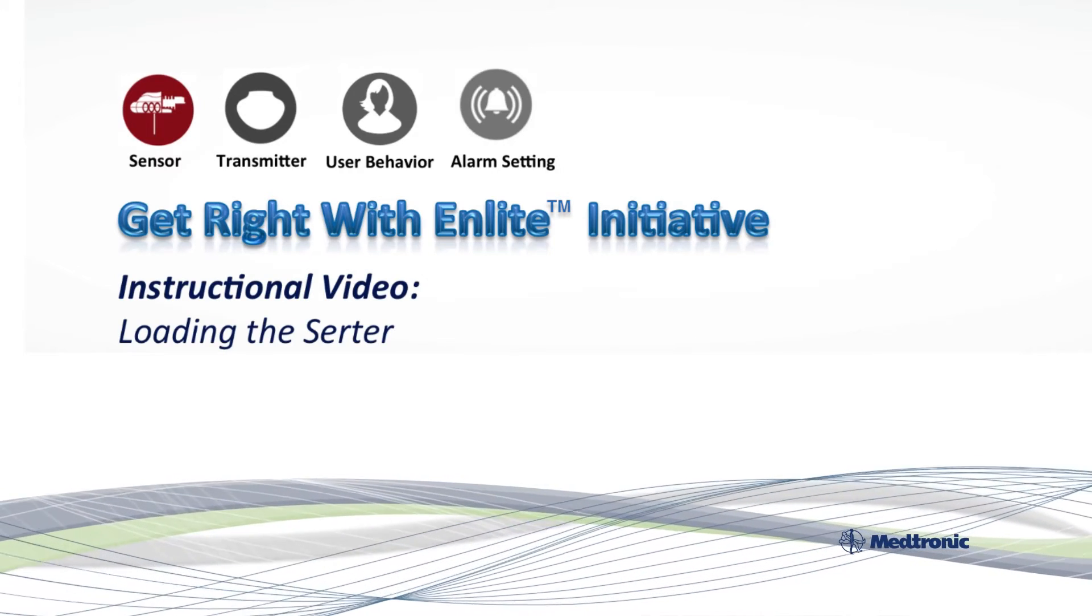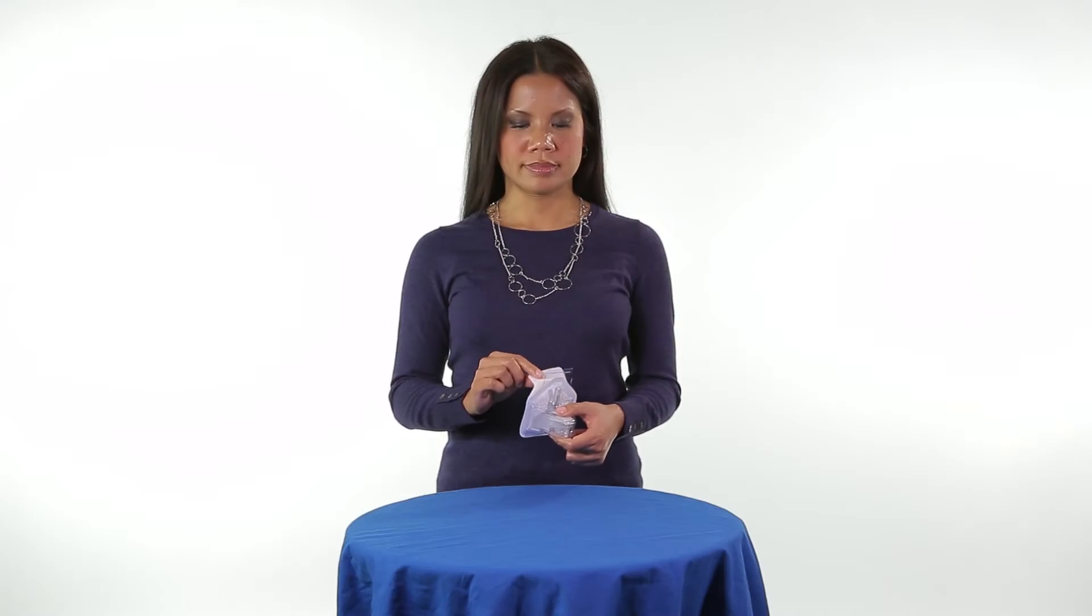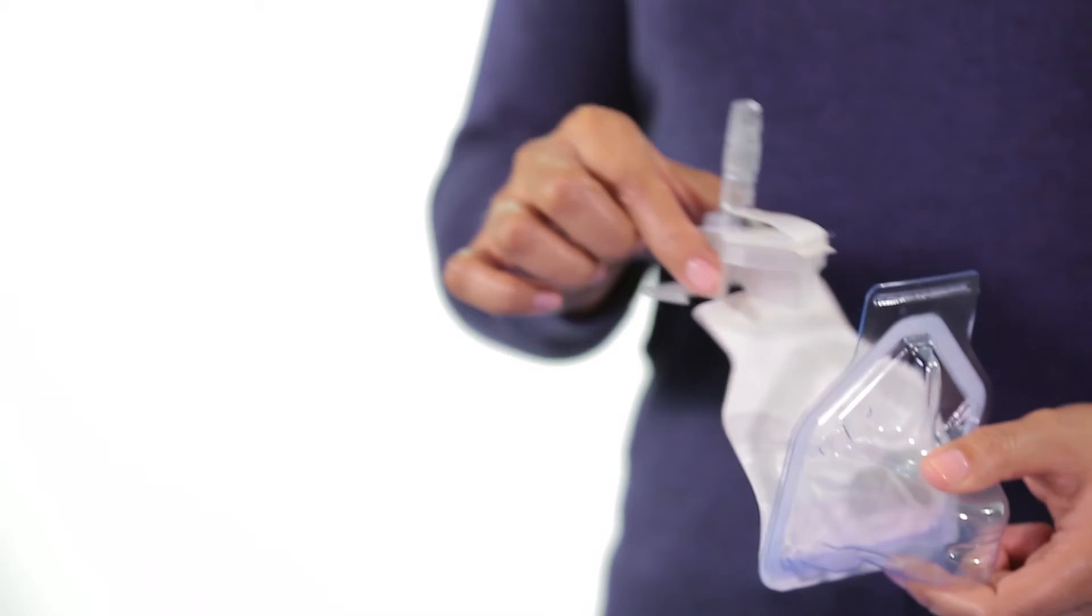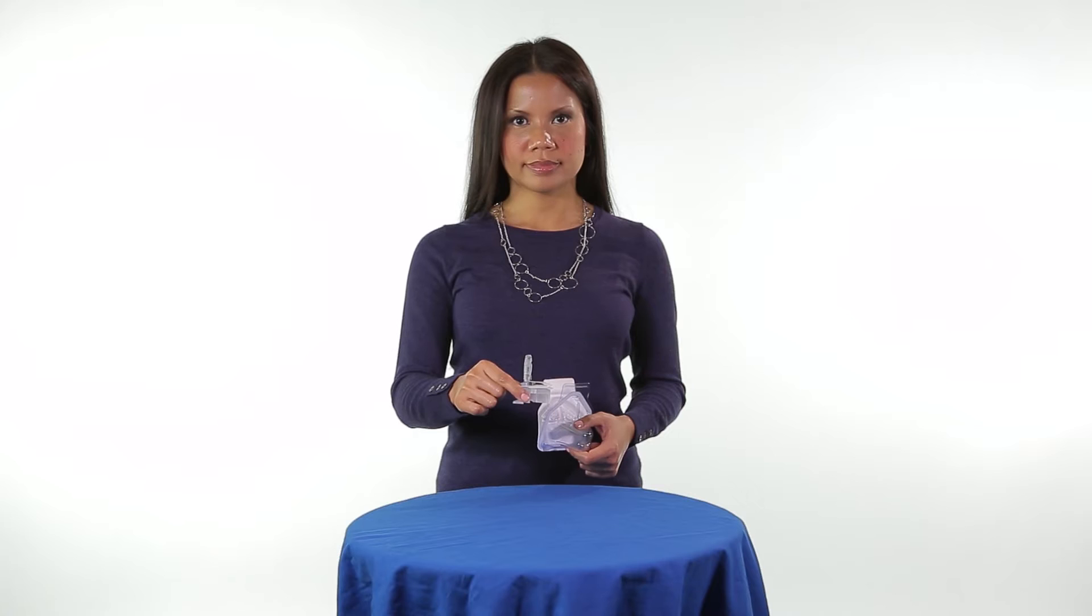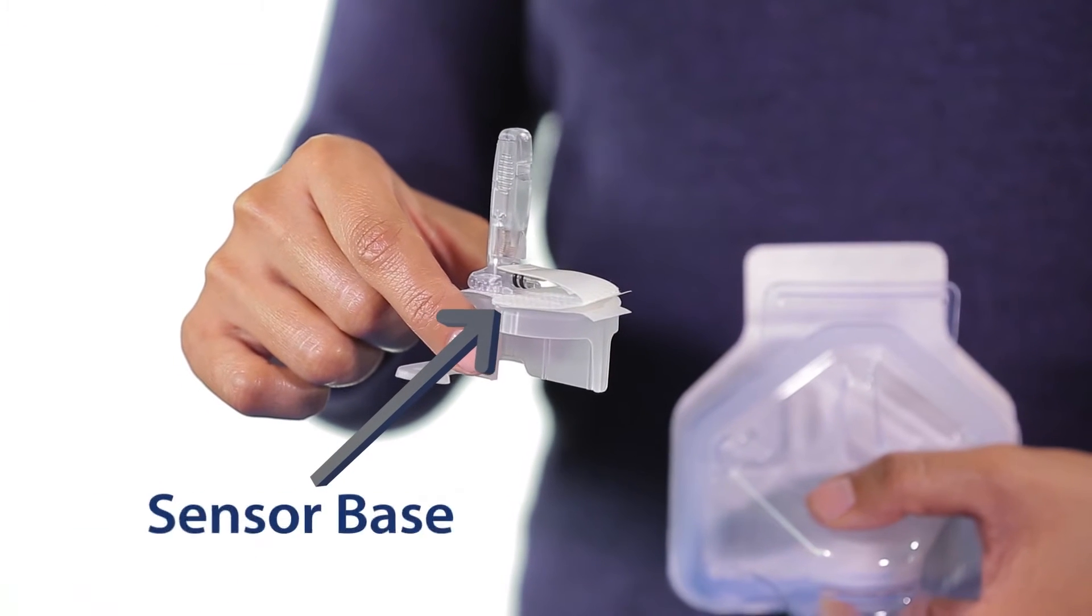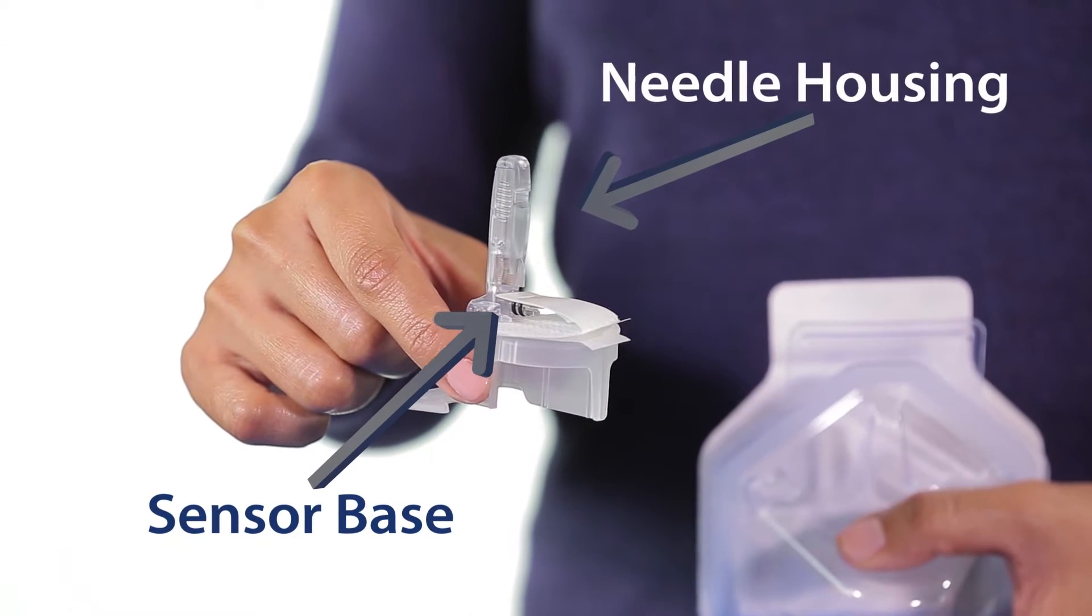Now let's talk about loading the sensor into the Serter. When removing the sensor from its packaging, you should hold the sensor by the plastic pedestal only. It is important that you don't hold it by the sensor base or needle housing, as this could damage the housing.